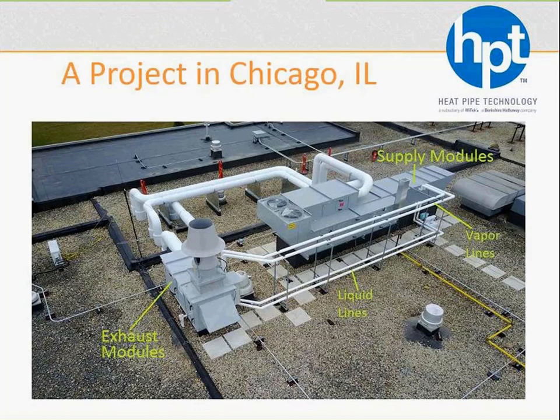Sharing this with you: a rep in Chicago had sent this to us, a recent project. Really neat. It looks like it was taken by a drone. On the right is your supply air handler. On the left is exhaust. I can tell by the number of pipes between supply and exhaust that this is a 4-row system: 2 tubes on top and 2 on the bottom, the top representing vapor, the bottom representing liquid.